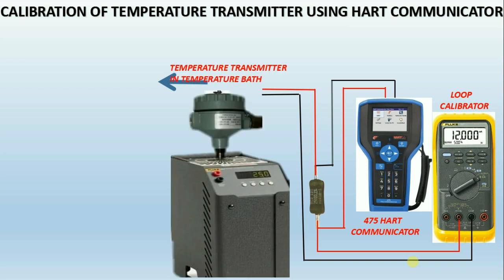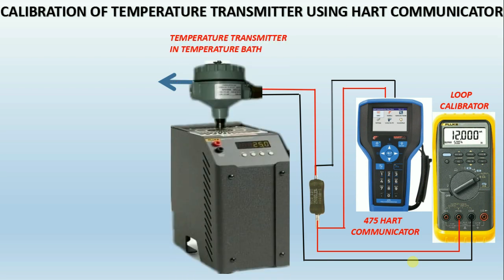Temperature calibration bath: if you need to calibrate temperature sensors with a portable calibrator, we will use this temperature bath for calibrating thermocouples, RTDs, thermistors, bimetallic switches, and more, with a temperature range spanning from minus 100 degrees Celsius to plus 1200 degrees Celsius.